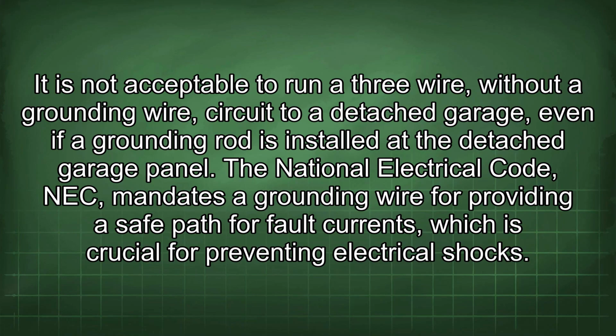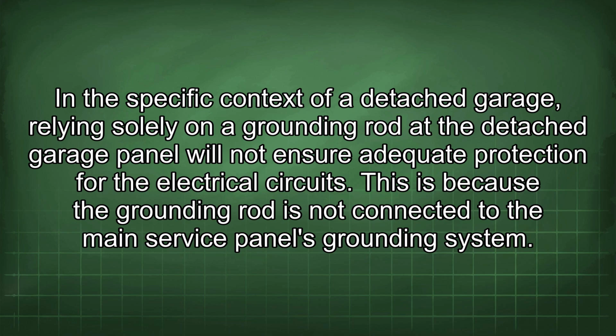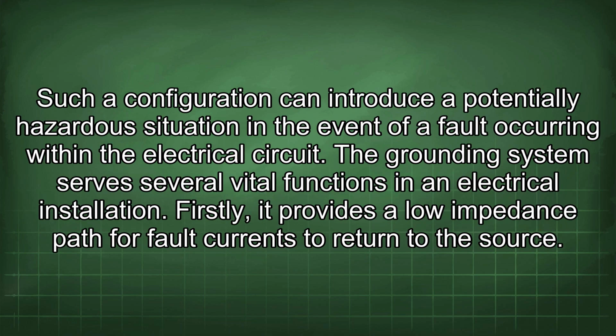It is not acceptable to run a 3-wire without a grounding wire circuit to a detached garage, even if a grounding rod is installed at the detached garage panel. The National Electrical Code (NEC) mandates a grounding wire for providing a safe path for fault currents, which is crucial for preventing electrical shocks. In the specific context of a detached garage, relying solely on a grounding rod at the detached garage panel will not ensure adequate protection for the electrical circuits. This is because the grounding rod is not connected to the main service panel's grounding system. Such a configuration can introduce a potentially hazardous situation in the event of a fault occurring within the electrical circuit.